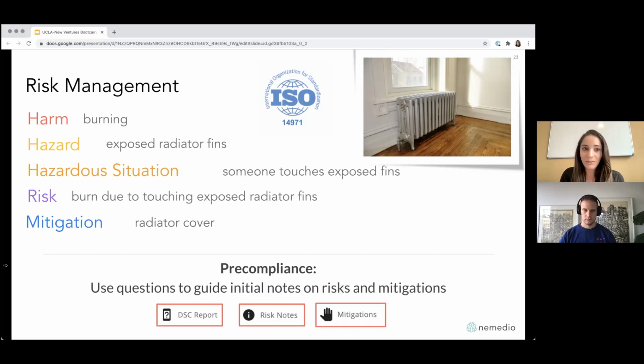And as good engineers building your device, you are already thinking about risks and mitigations. You might not go into detail in a compliant way about the harm and the hazard and the probability and the severity and the likelihood, all that stuff. But what you are doing is saying, oh, I'm going to build this part, I'm going to make this piece a little bit thicker because if this piece breaks, it's going to cause this other thing to break. And then the device won't function properly. And what you just did is you identified a risk in your head and you identified a mitigation. And the important part for pre-compliance is that you keep track, in plain English, of the things that you're already doing to mitigate the risks of your medical device.